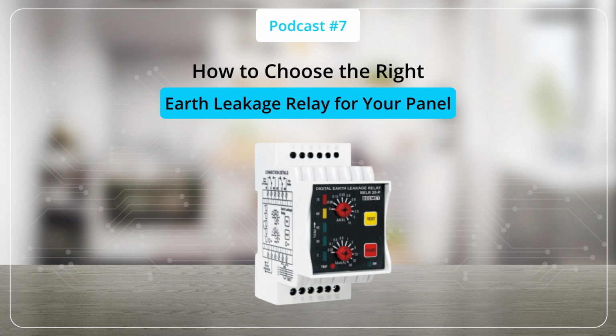Now let's look at the role of earth leakage relays in industrial electrical control panels and systems. Industrial panels are often responsible for controlling heavy electrical loads, including motors, power distribution systems, pumps, and variable frequency drives, also known as VFDs. In these systems, earth leakage relays work alongside core balance current transformers to continuously monitor electrical currents flowing through phase and neutral conductors. When leakage occurs, the ELR quickly trips the breaker and disconnects the circuit, helping protect personnel and equipment.